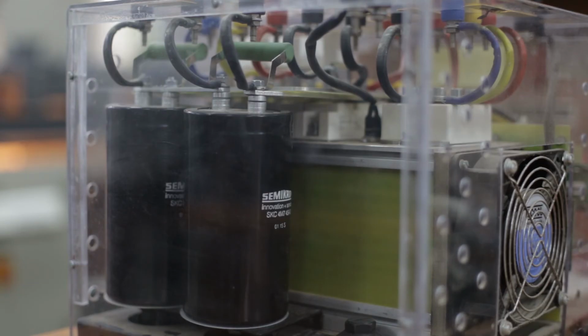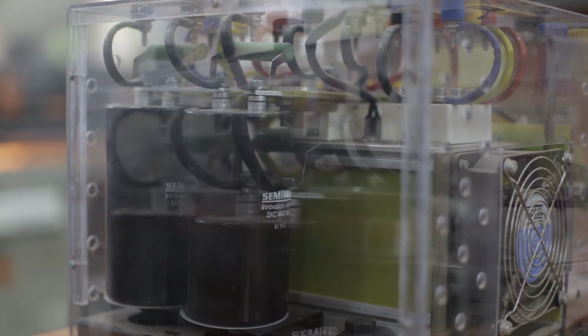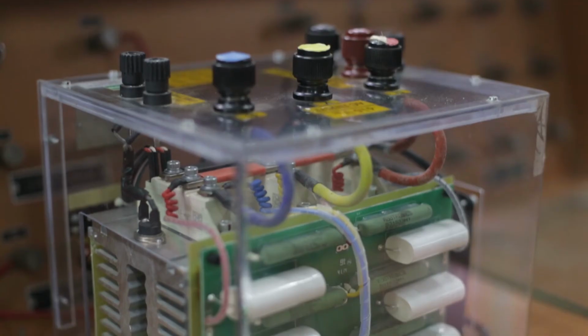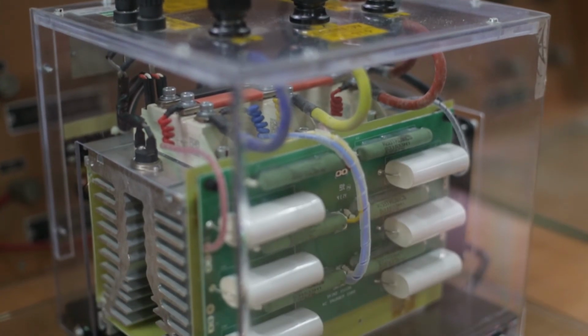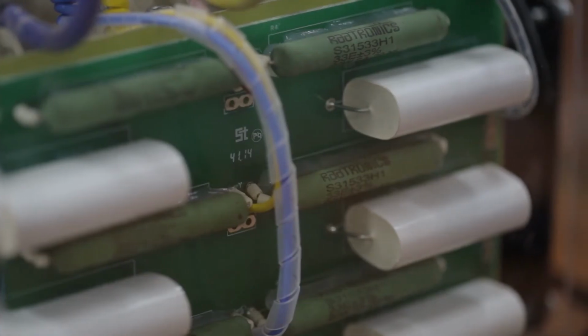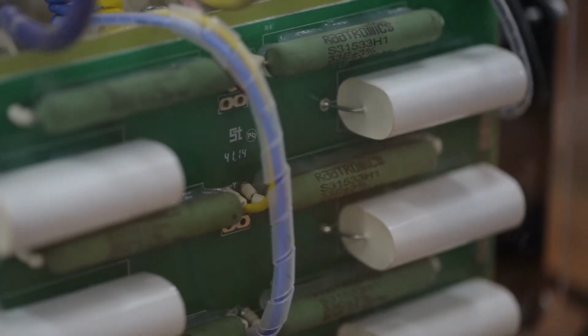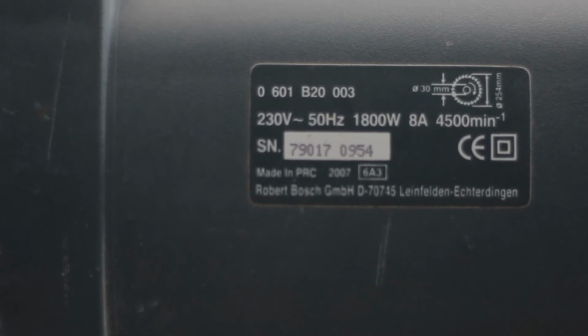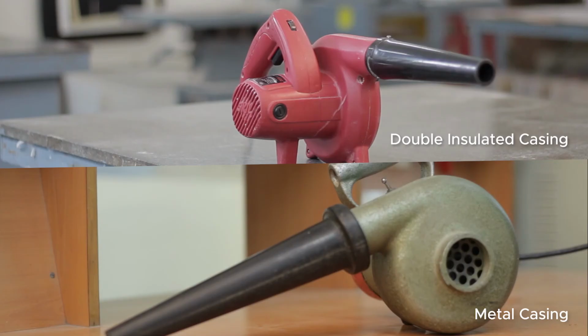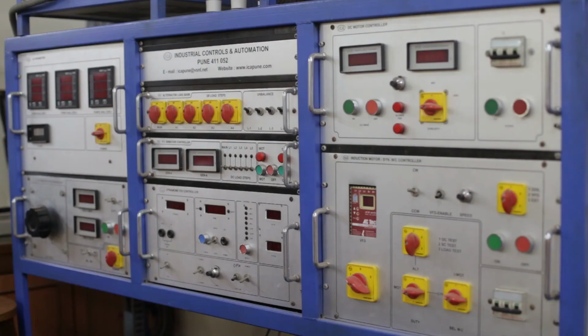If capacitors are used for research work, they must be fully discharged before working on them. Capacitors can cause impact shocks. Capacitors must have bleeder resistors across the capacitor terminals for discharging. Electric power operated tools shall either be of the approved double insulated type or must be grounded.